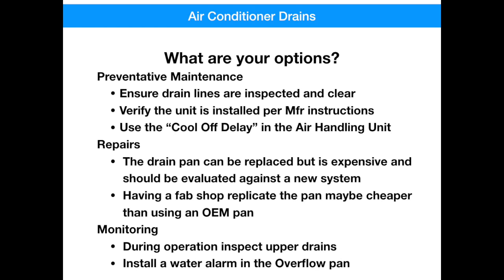As for monitoring, you should periodically inspect your outside drains for signs of rust. And as far as the upper drain lines, you should never see anything leaking from them at all. Be sure to do this inspection after your AC's been running for a couple hours.